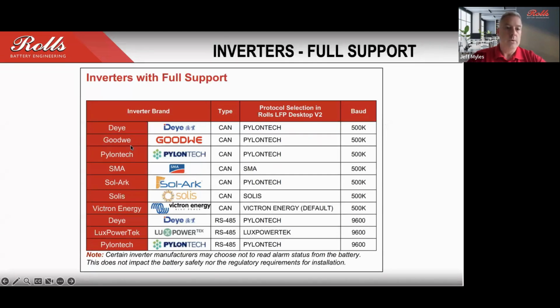So when you're connecting these units, what we've done in the manual is divided up the inverters into essentially two different lists based on the capability with reference to closed loop communication and the information that's shared. So the first list is essentially offering full support. One thing that happens with the ESS units, and it's very standard across most of these, is that the BMS is capable of sharing information related to battery voltage, temperature, cell temperature, and so on. But in some cases, the inverters may or may not use that information and share it, whether it's on screen or through a remote application or whatever.